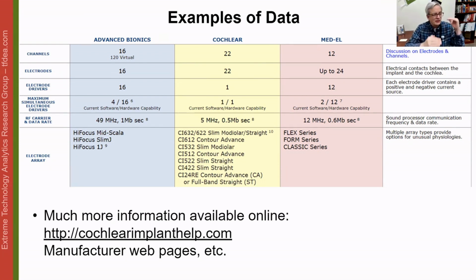The RF carrier, or radio frequency carrier frequency, varies - 49 megahertz, 5 megahertz, 12 megahertz, different values. But perhaps more importantly, the data rate tells you the maximum amount of data you can transmit across this barrier. Advanced Bionics designs theirs at 1 megabit per second, Cochlear at 0.5, and MED-EL at 0.6. This essentially tells you the maximum data speed.